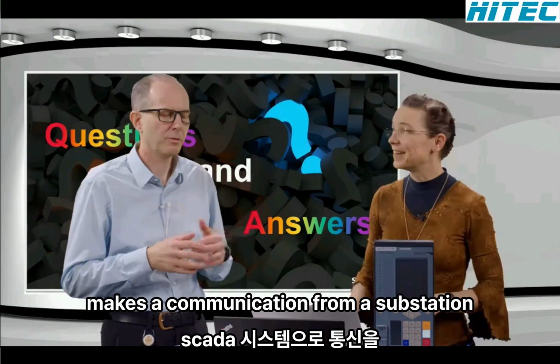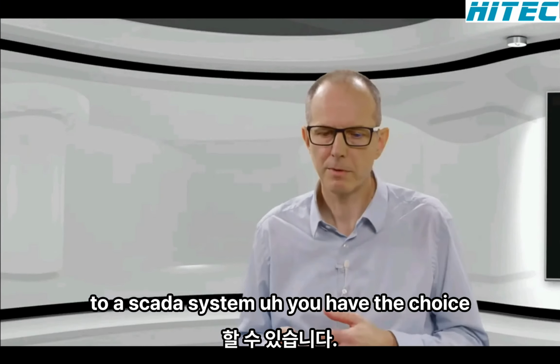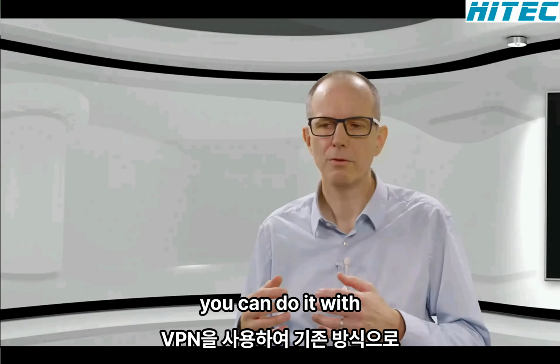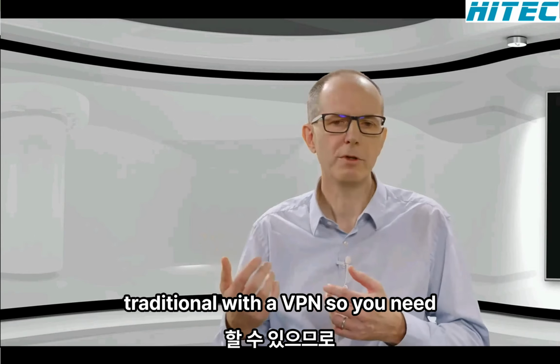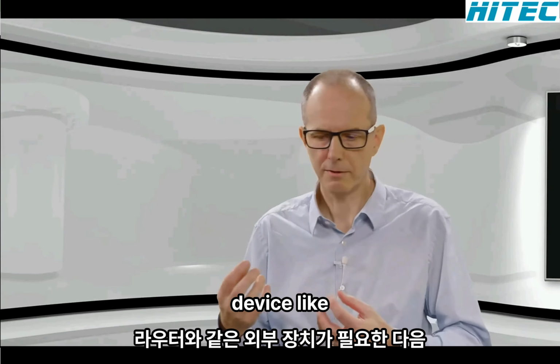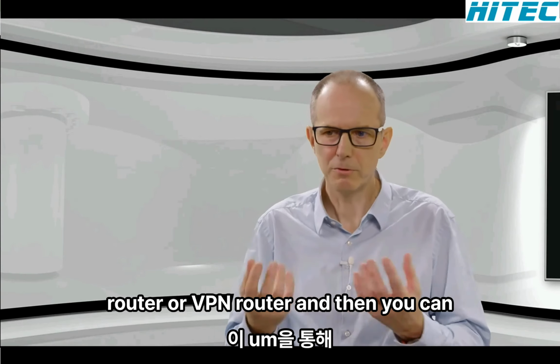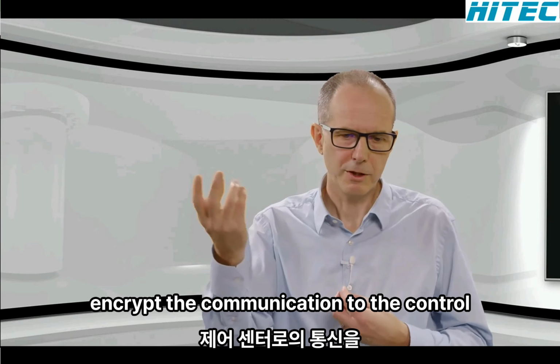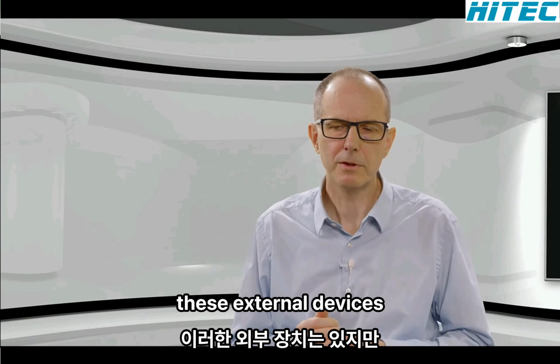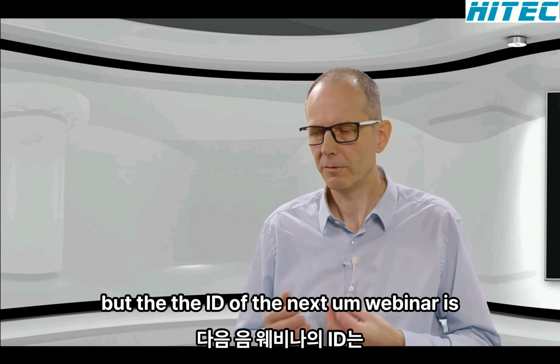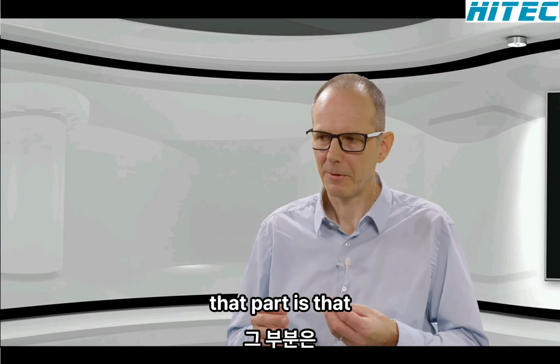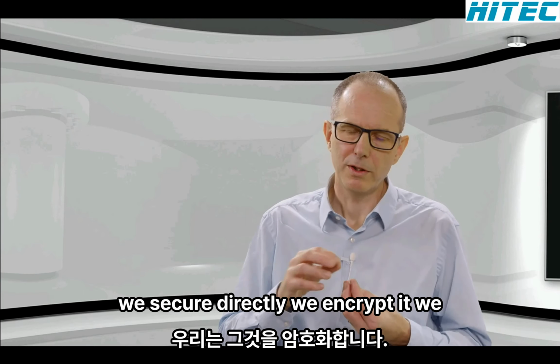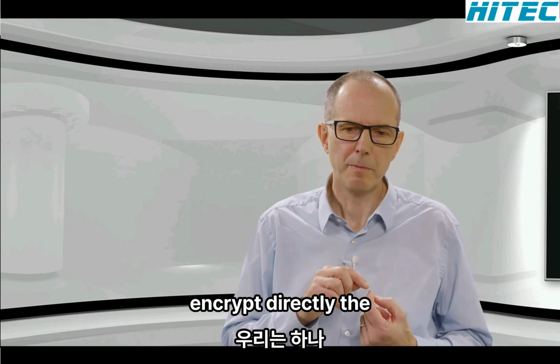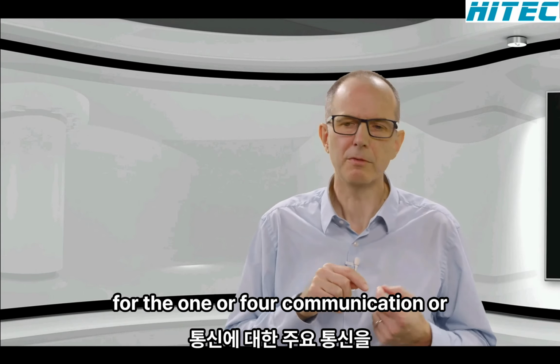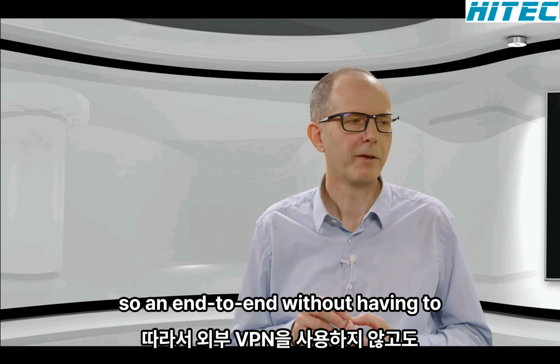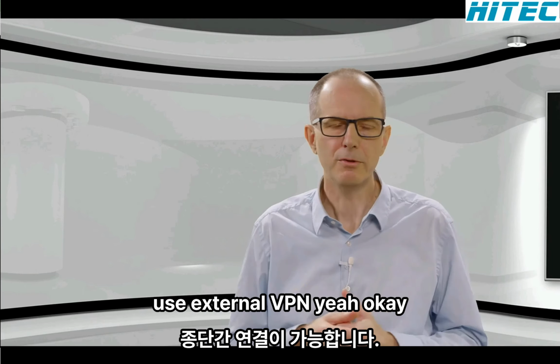Maybe to clarify, to make the communication from a substation to a SCADA system, you have the choice. You can do it traditionally with a VPN, so you need an external device like a router or VPN router, and then you can encrypt the communication to the control center via these external devices. But the idea of the next webinar is that we secure directly, we encrypt directly the main communication, so the 104 communication or the 61850 communication.